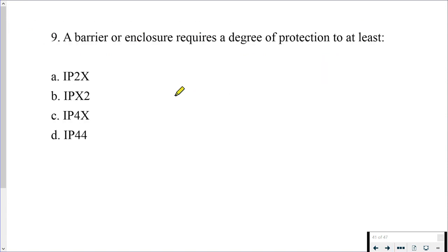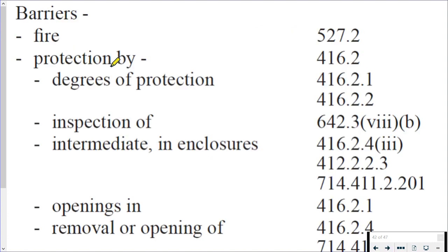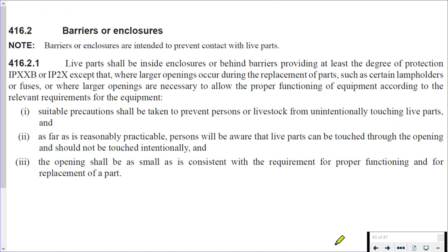Question 9: a barrier or enclosure requires a degree of protection to at least, and then we've got these IP codes. So wherever it is we're going, we are skimming for IP codes. We're looking at barriers or enclosures, we're also looking for this term 'at least,' and we're looking for degree of protection as well. So barriers or enclosures in the index, we have degrees of protection, and we've got 416.2.1 and 416.2.2. If we look at 416.2.1, there you go, straight off the bat we've got IP codes, and then reading around about the IP codes we see that at least a degree of protection, there you go, IPXXB or IP2X.